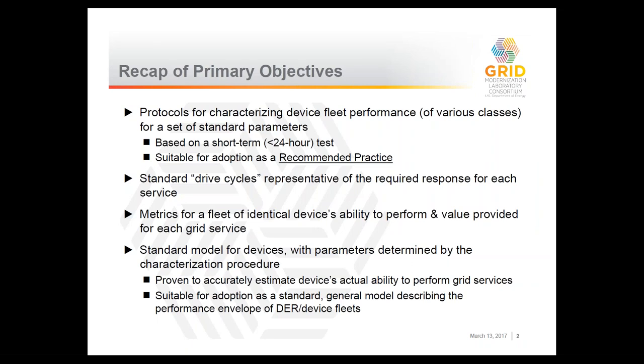What we are trying to do here, as David mentioned, is, for a device, come up with the protocols for characterizing a device fleet performance. So it is very important to understand that one single distributed device is probably not going to provide this type of megawatt-scale grid service. So we need a fleet of devices. So we are assuming whatever we are doing on a device can be translated into a big fleet.